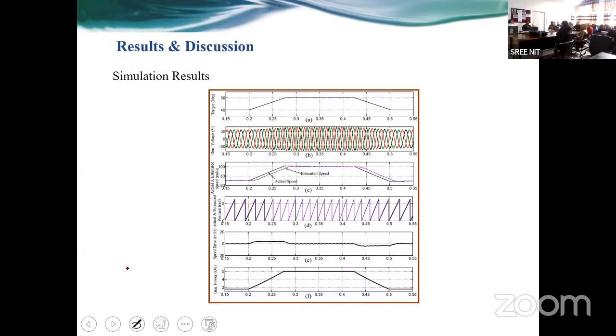Yes, please. Any other? In case of theta, you told that theta is from the grid. What if we take the voltage to the PLL on the generator side? No, you can, but then the generator side operation will be faulty, because it is synchronized with the grid current and grid theta. Here the purpose is to control the speed of the generator. So you must know at what speed it is actually rotating. If you give it the wrong theta, wrong speed operation will take place. So that is not desirable.